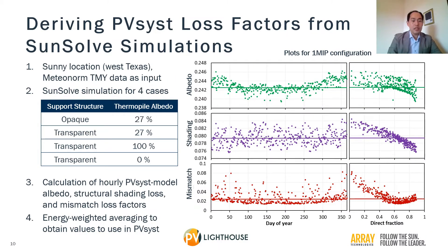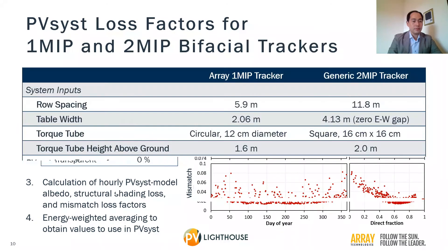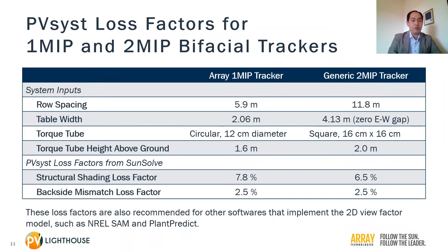Here are the loss factor values that we obtained from the PV Lighthouse study. We obtained values for the Array 1-module-in-portrait tracker as well as for a generic 2-module-in-portrait tracker. The structural shading loss factor is slightly lower for the 2MIP tracker, but not by a lot. The mismatch loss factors are identical. The 2MIP tracker was simulated with no gap between the east and west modules, and the reason will be explained in a later slide. Although these loss factors were obtained for PVsyst, we recommend these values for other software that implement the 2D view-factor model, such as NREL-SAM and PlantPredict.